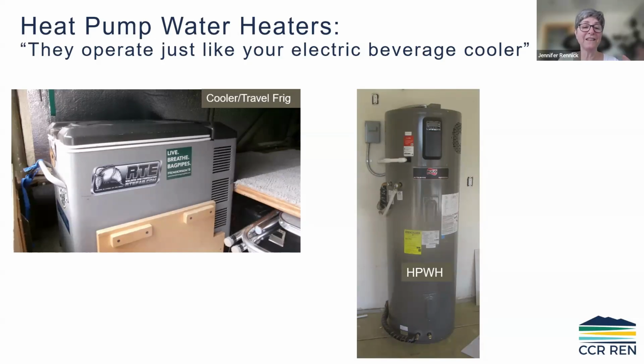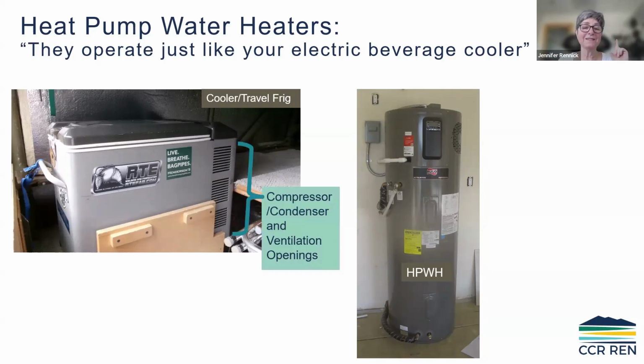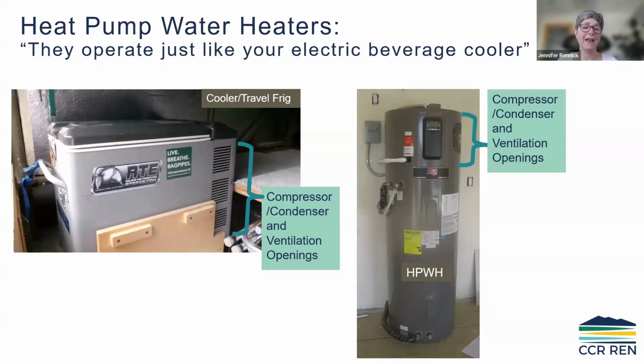This picture on the left is from the back of the pickup truck of one of the guys in the field. He does our HERS rating. He's got a cooler traveler fridge. A bunch of folks have this when they go out hunting, but they don't realize you've got a compressor and condenser, a little heat pump right there, and it's got ventilation openings. And you go to your heat pump water heater, and up at the top of the tank for the integrated type, you have your compressor, condenser, and ventilation openings.